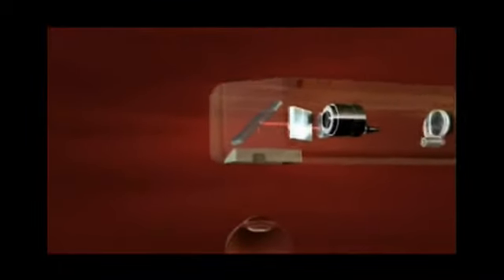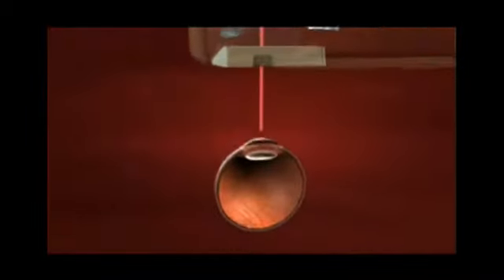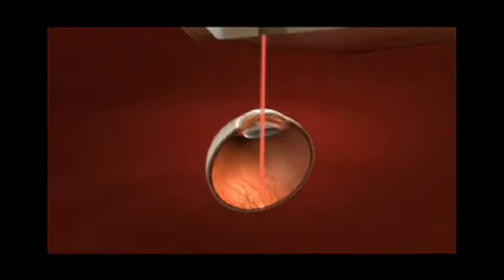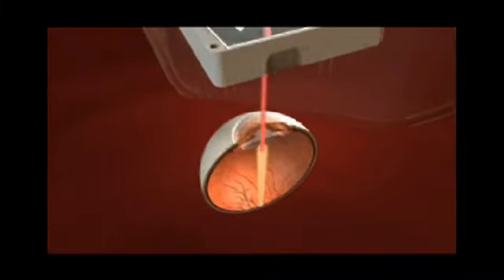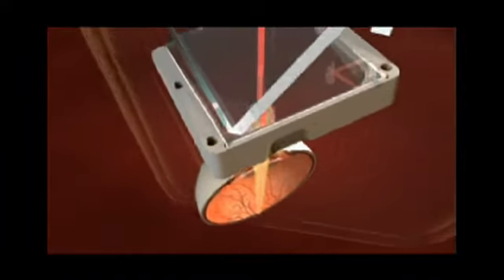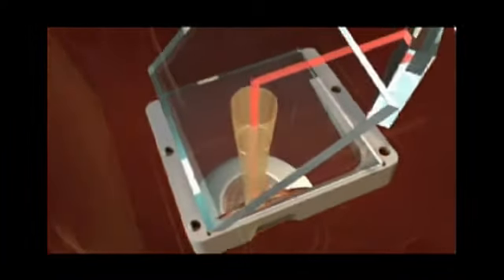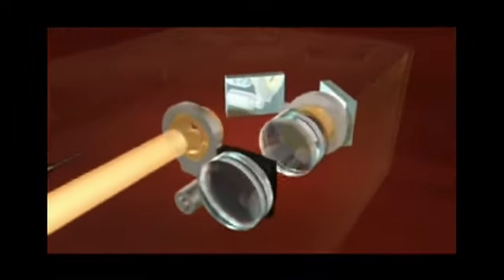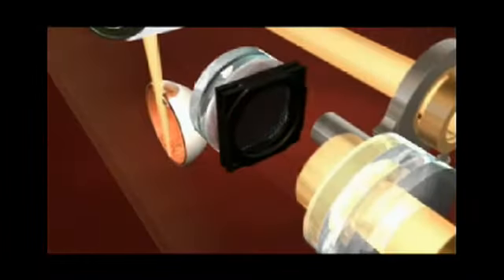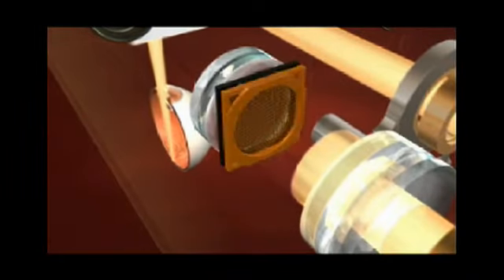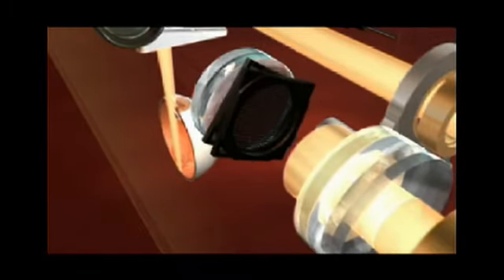When a wavefront image is taken, a narrow beam of light is directed into the patient's eye and is reflected off the retina. As the reflected light passes back through the optical elements of the eye, it produces an aberrated wavefront. ORA analyzes the wavefront reflected out of the eye by relaying it through an optical system and directing it through a pair of gratings set at a specific distance from and angle offset to each other.